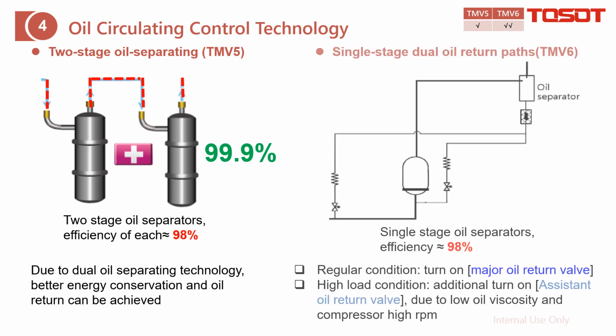As for TMV6, the oil separator is only one, but with two oil return paths. And here is how it works. This is the compressor, and here is the oil separator. The oil and refrigerant mixture will go through the oil separator. The refrigerant will go into the system for heat exchange, and the separated oil will go through this filter and then get through. First is the major oil return, back to the compressor for lubrication. At that time, this major oil return valve is always open.